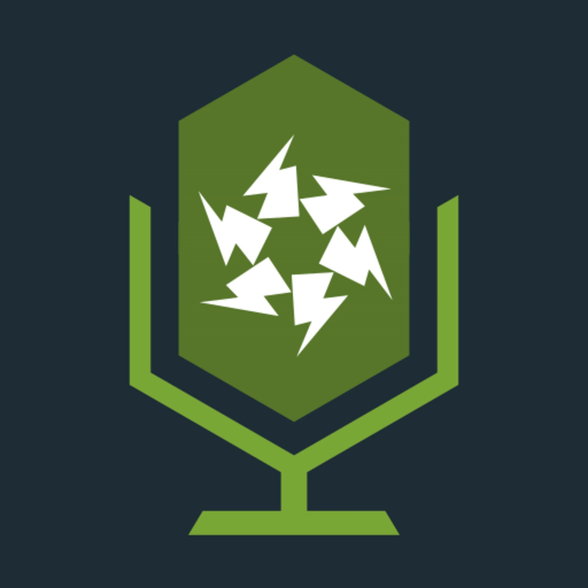Because if we used it, they could take it away, they could replace part of it, and so its value is obviously not controllable. But then the extraneous conductive part comes into the building, but then it goes off and becomes an extraneous conductive part again, because it goes back underground. So this is something that I mentioned back in, I think, chapter 41 when I talked about kitchens and things with cables going underneath. If you put a pipe underground, it becomes an extraneous conductive part again.